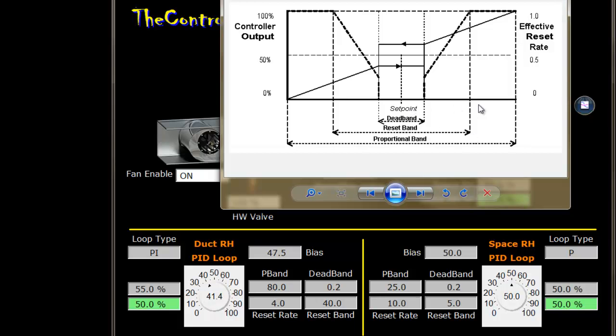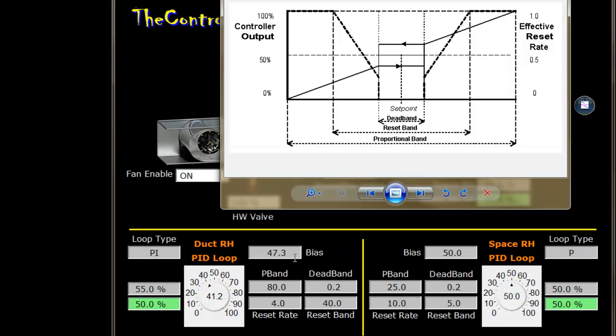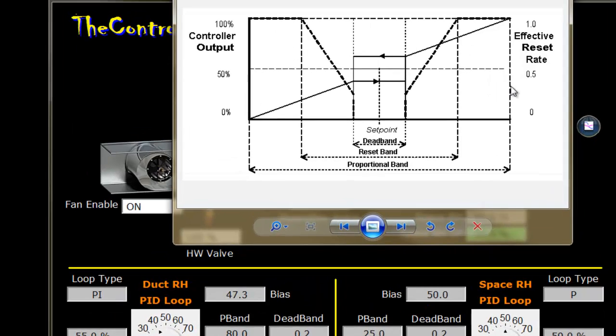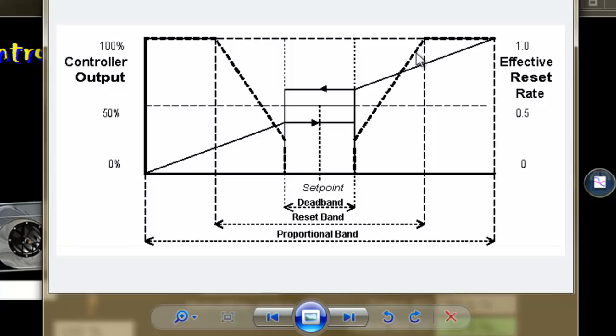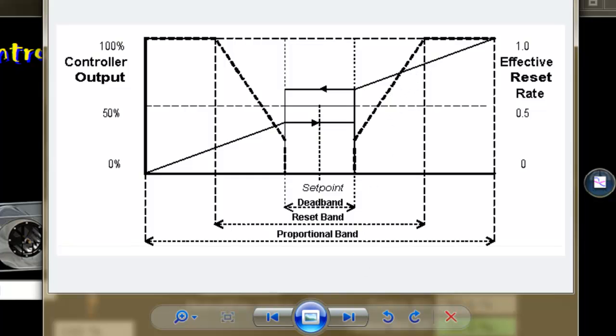Because you have to remember we're talking of a span of 40, so if we're 20% away from set point, we're at the limit up here at 1.0. We're going to utilize the full reset rate of 4. This bias, if we waited one minute, would move from 50 to 46.